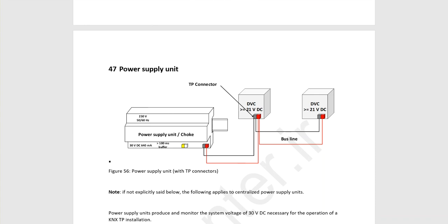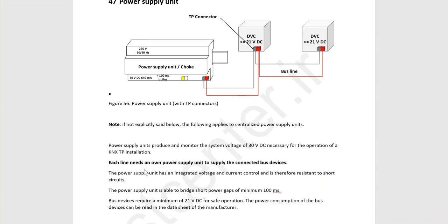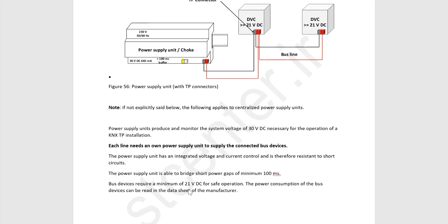Okay, the power supply units. First of all, each line needs its own power supply unit to supply the connected bus devices. Remember that. Even in a classical topology, the main line and the backbone line have their own power supply units. Bus devices require minimum 21 volt DC for safe operation. The power consumption of the bus devices can be read in the datasheet. I said before that we should always read the power that the device uses and consider it to select the right power supply.